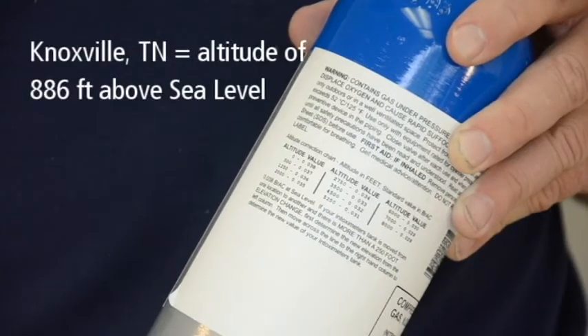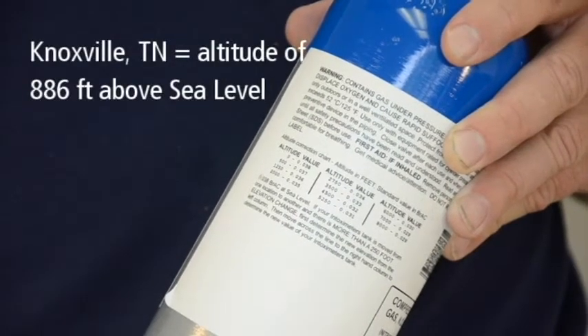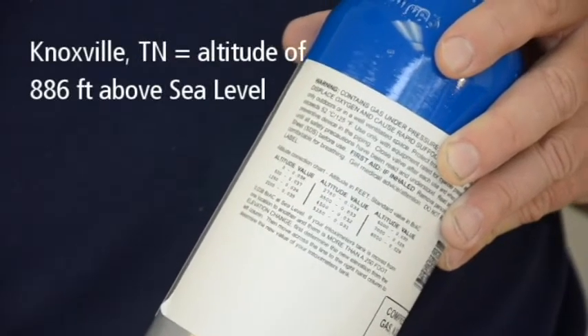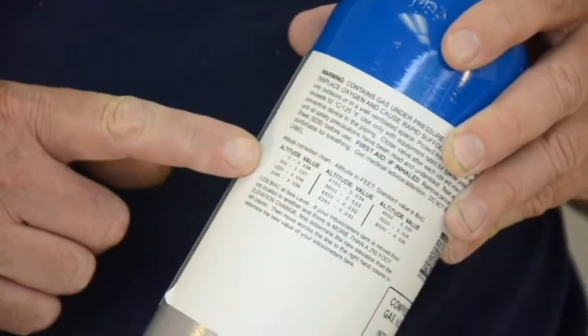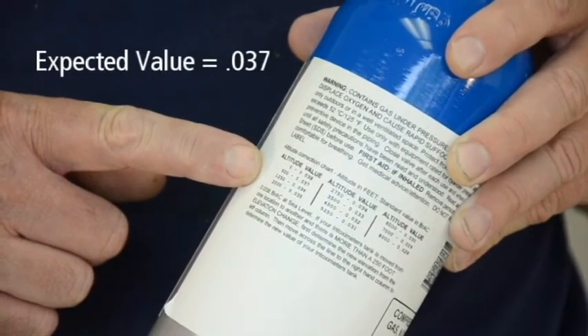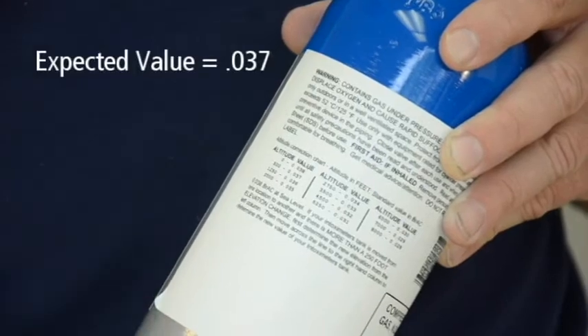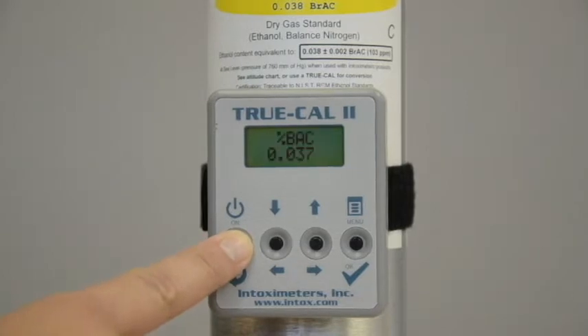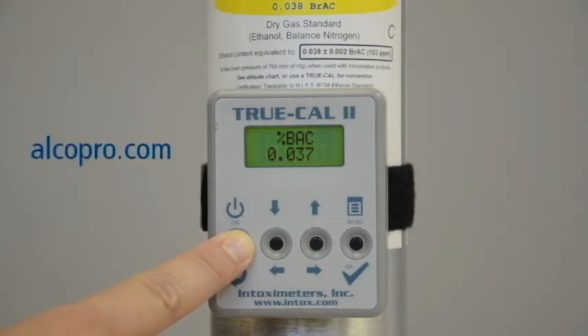For example, if you are performing an accuracy check in Knoxville, Tennessee, which has an altitude of 886 feet above sea level, the altitude chart shows the expected value of the alcohol gas tank to be .037. You can also derive the expected value by using a True-Cal device, which uses atmospheric pressure to predict the expected value of the gas. You can purchase a True-Cal device at alcopro.com.